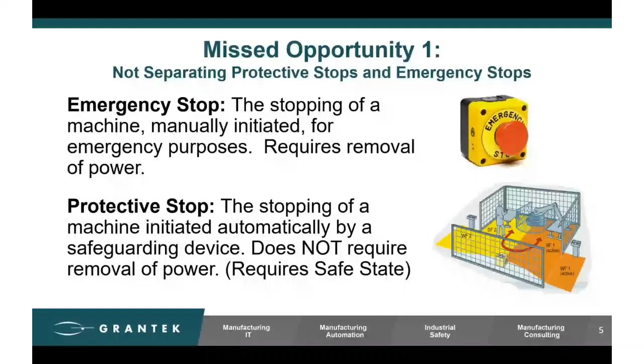Most companies, and most engineers, remove power for both their emergency stop devices and their safeguarding devices. Now, is this allowed? Is it okay? Well, sure. As long as your emergency stop removes power and your safeguarding device puts the machine in a safe state, which we'll assume removing power accomplishes, then you can absolutely combine them. There's nothing wrong with this method. In fact, we probably see it over 60% of the time. It just misses out on other possibilities.